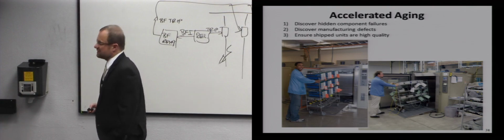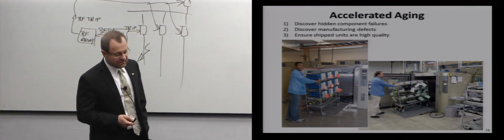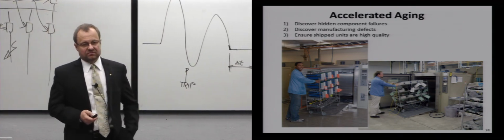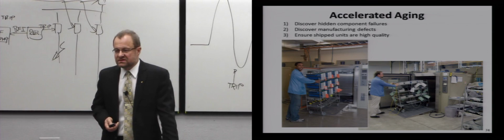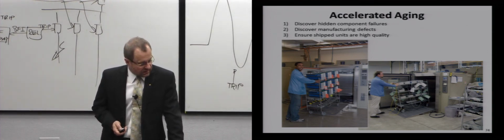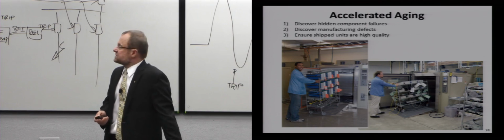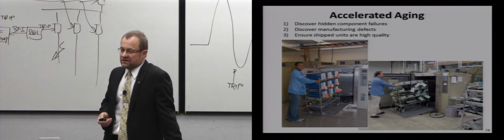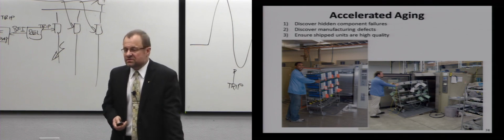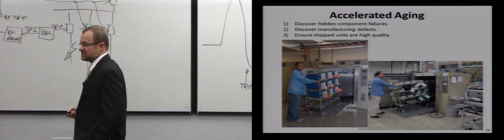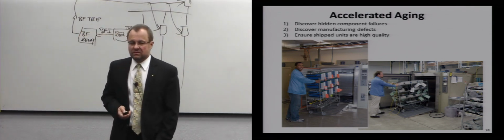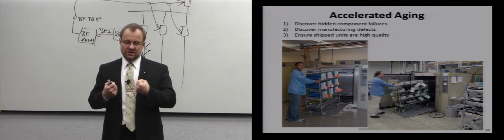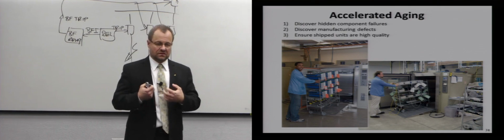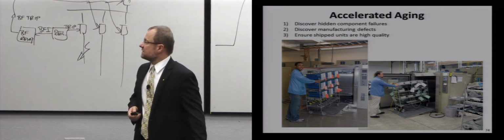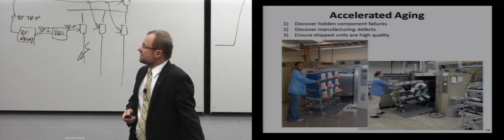What we do in manufacturing, we follow a burn-in process, meaning that if something is wrong, if a wrong part got populated, or there is a part defect, or somebody on the Monday morning shift had too much fun over the weekend and didn't follow the procedures, we want this stuff to fail in our factory before we ship it. So we put those relays in the oven, we cycle temperature very fast, from very cold to very hot. The printed circuit boards are really stressed. If there is poor quality solder or other defects, they will show up and the devices will fail. And this way we will not ship them and we will not cause a problem to anybody.